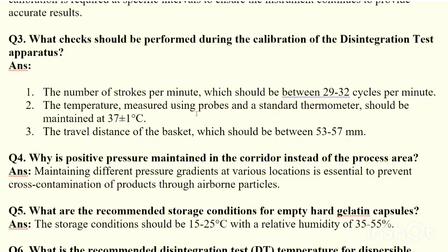The number of strokes per minute should be between 29 to 32 cycles per minute for DT calibration. Temperature is measured using probes and a standard thermometer, and should be maintained at 37 ± 1°C. The travel distance of the basket should be between 53 to 57 mm. These are the key checks during DT calibration.